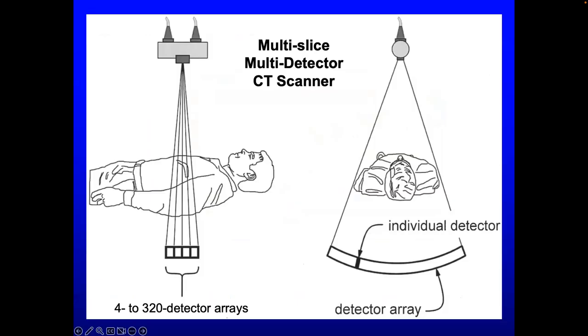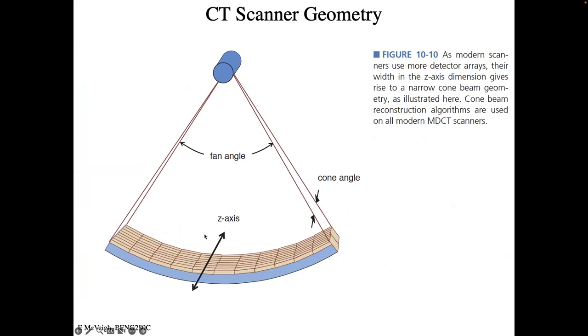Multi-detector CT is conceptually simple: you stack detector rows so that instead of a 1D detector with a fan angle, you now have a 2D detector with both a fan angle and a cone angle. There are some artifacts associated with a wide detector because beams emerge at different angles depending on source position. Sixty-four rows in the z-direction is now the minimum commonly seen.